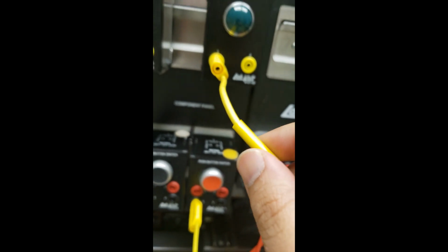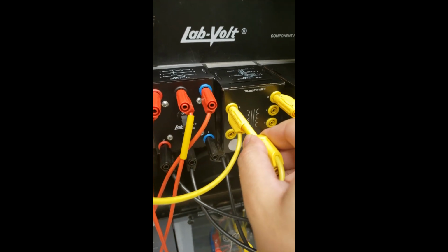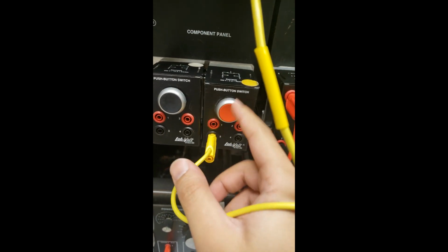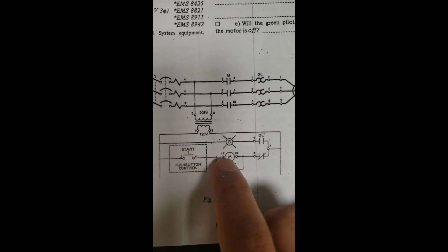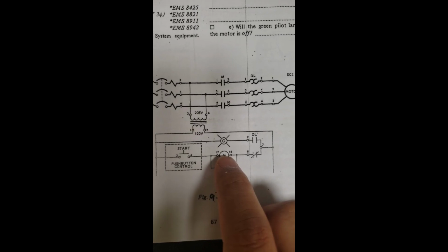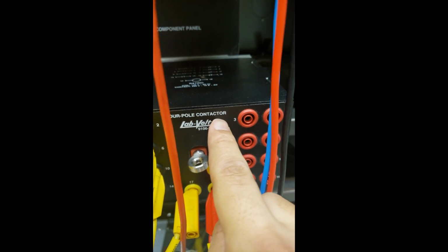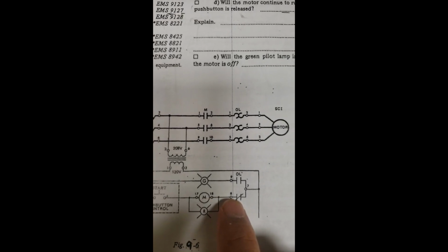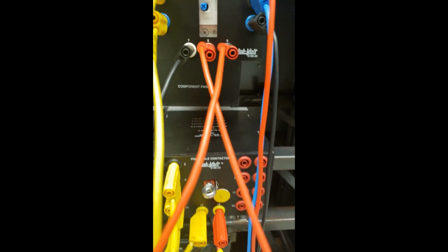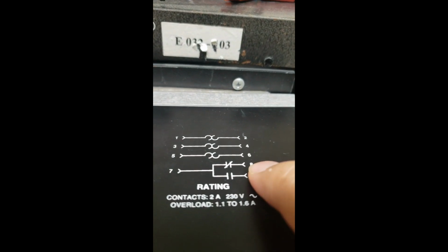From 1 of the transformer to the green light, and the same from 1 as well to the 3 of the push button, both of them from 1. Now from 4 of the start push button to the terminal 17, the coil of the contactor. So from 4 to 17, from 4 push button to 17 of the contactor. Okay, then from 18, the coil of the contactor, to 8, the normally closed overload relay. From 18 to 8, the normally closed contacts.